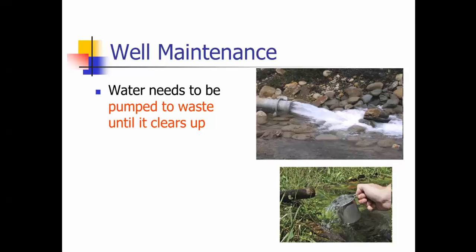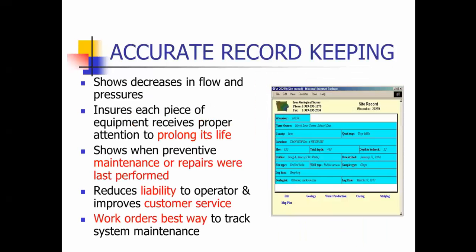On well maintenance, the water needs to be pumped to waste until it clears up before you put it in line. Once you start a well up, it needs to clear up and make sure that it has a turbidimeter, or you're testing it with some type of something to check and make sure that it's cleared up before you put it in line. You want to keep accurate records.